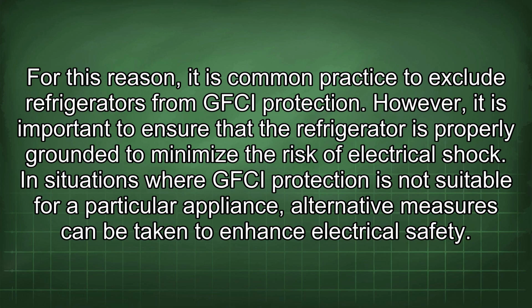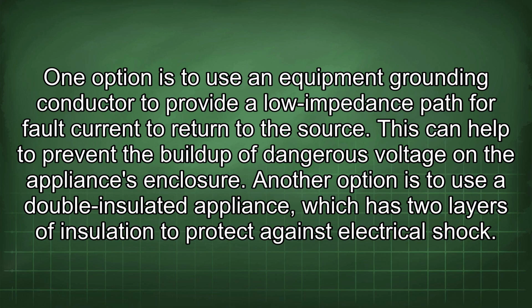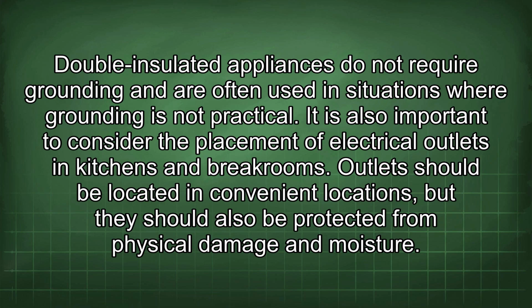In situations where GFCI protection is not suitable for a particular appliance, alternative measures can be taken to enhance electrical safety. One option is to use an equipment grounding conductor to provide a low impedance path for fault current to return to the source. This can help to prevent the buildup of dangerous voltage on the appliance's enclosure. Another option is to use a double insulated appliance, which has 2 layers of insulation to protect against electrical shock. Double insulated appliances do not require grounding and are often used in situations where grounding is not practical.